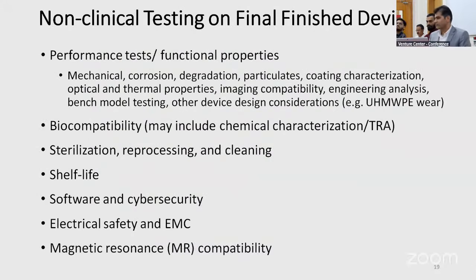All right. Now coming to a couple of final slides, the non-clinical testing itself. There is the performance test, the functional test. These are mechanical, corrosion, degradation kinds of tests. This usually comes in during product development itself, in your QA/QC, when you're seeing if your prototype actually works the way you intended it to work. But again, when you have a final finished device, all of this testing will have to be done again on the final finished device, one that is already sterilized, as a representative device.